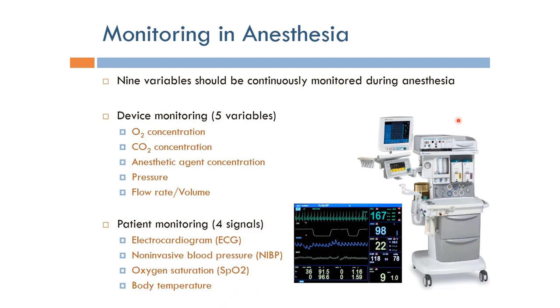For regular or advanced modern anesthesia machines like this, usually you will have a screen that has the patient monitoring and another for the device monitoring. Sometimes you can get both on the same screen, but it's very important for the anesthesiologist to monitor all these parameters so that he can notice any changes that happen during the surgery and make sure that the patient is safe.